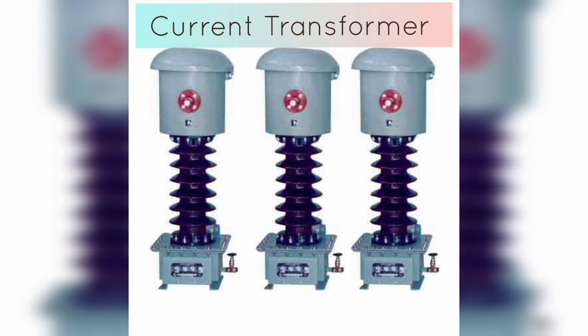CTs are commonly used in power systems to measure and monitor the current flowing through transmission lines, distribution lines, and electrical equipment such as generators, transformers, and motors. They are also used for protective relaying, detecting and isolating faults by sensing abnormal current levels and triggering protective devices. CTs are designed to operate at a specific frequency and current range and must be properly selected and installed. Additionally, CTs must be calibrated periodically to ensure their accuracy over time.